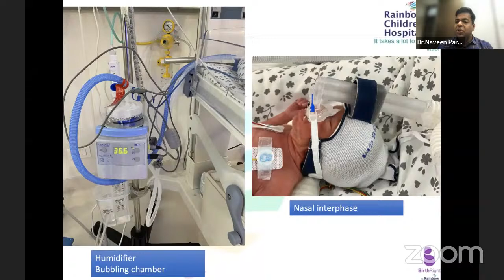Then if you don't have a blender, suppose you can't spend so much money on that, you can keep this chart and always remember this formula. In the formula, suppose you are giving 4 liters of air and 4 liters of oxygen. Always remember that air also has 21% oxygen. So you multiply 0.2 into the airflow, 0.2 into 4, plus oxygen is 100%, so 1 into 4. So this becomes 4.8 divided by the total flow, that is 8. So it is 60%. If you are giving the same flow rate of air and oxygen, 4 and 4, or 3 and 3, then the FiO2 will be 60%.